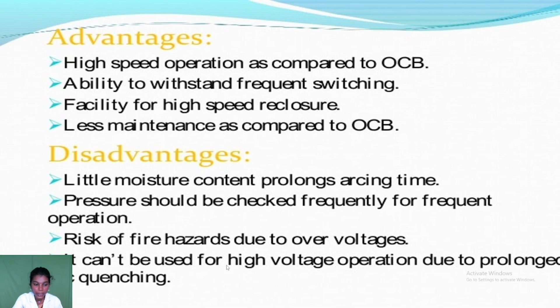So next we move on to the SF6 circuit breaker. I already told that SF6 is nothing but a sulfur hexafluoride circuit breaker. A circuit breaker in which SF6 gas under pressure is used to extinguish the arc is called a sulfur hexafluoride circuit breaker. This gas has excellent dielectric, arc quenching, chemical and other physical properties, which have proved its superiority over other arc quenching media such as oil and air.